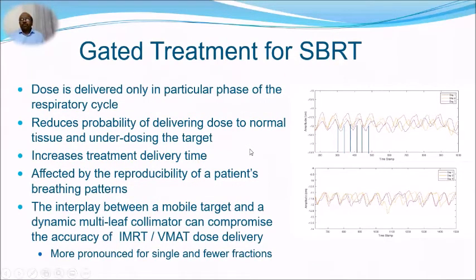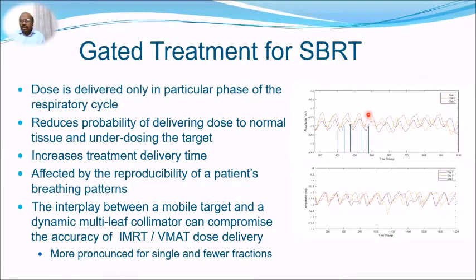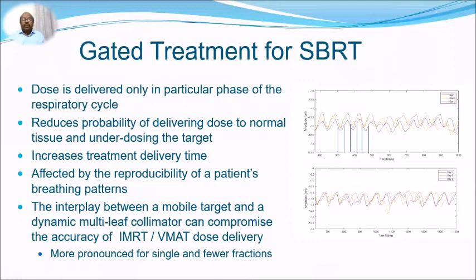Gated treatment is another option for SBRT. In gated treatment, the dose is delivered only during a particular phase of the respiratory cycle. The beam is on only when the patient's breathing reaches the designated phase; during the rest of the breathing cycle the beam is off. This reduces the probability of delivering dose to normal tissue or under-dosing the target, but it increases delivery time because the system waits for the patient's breathing to return to the correct phase.